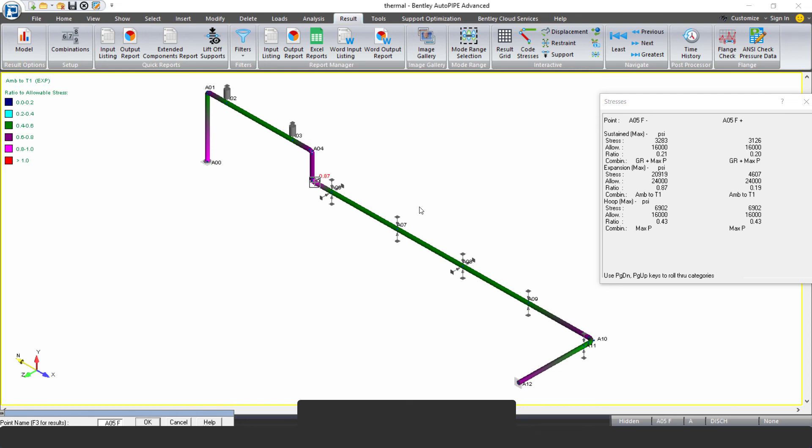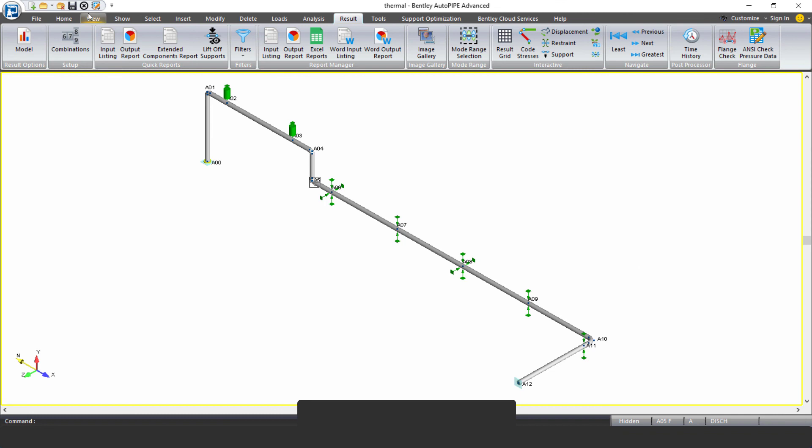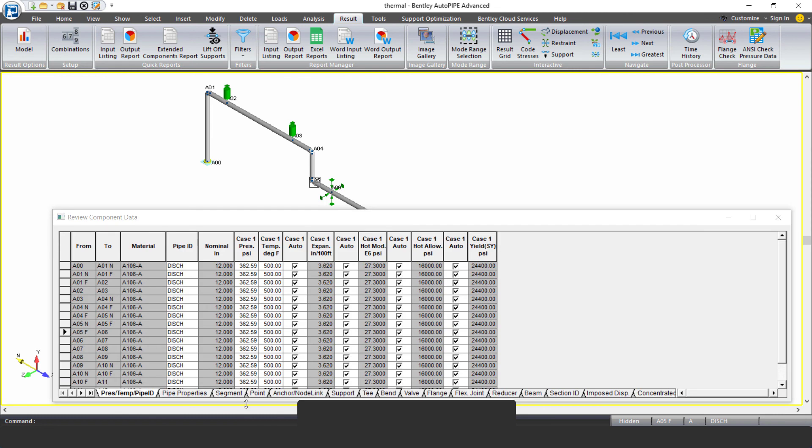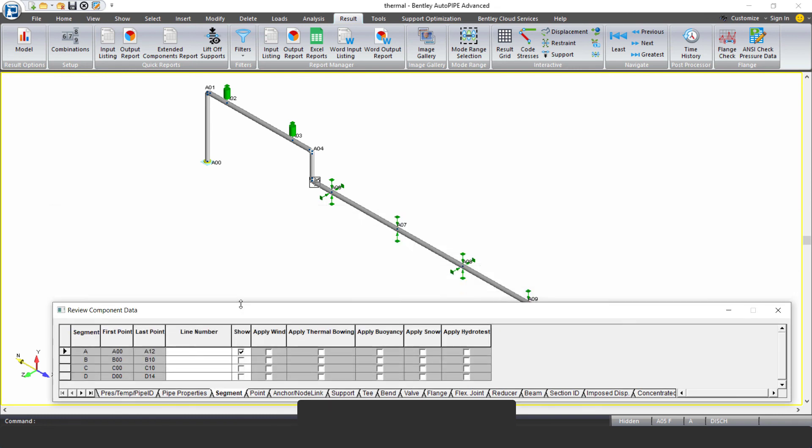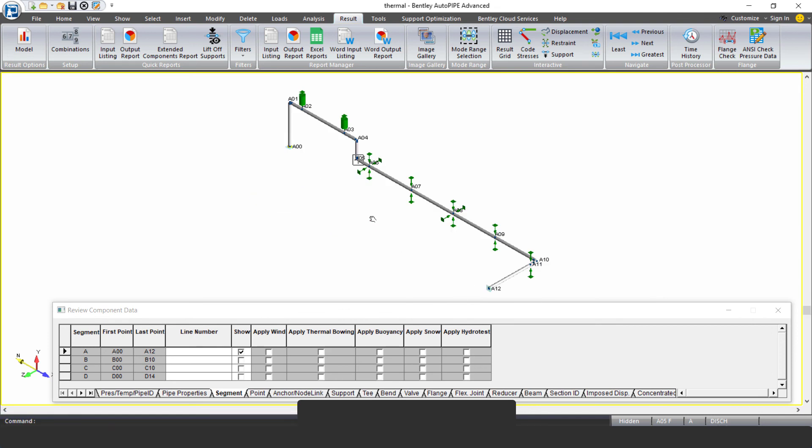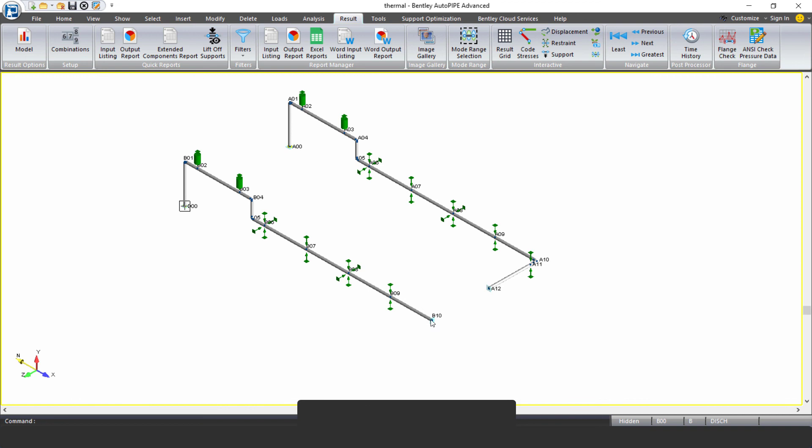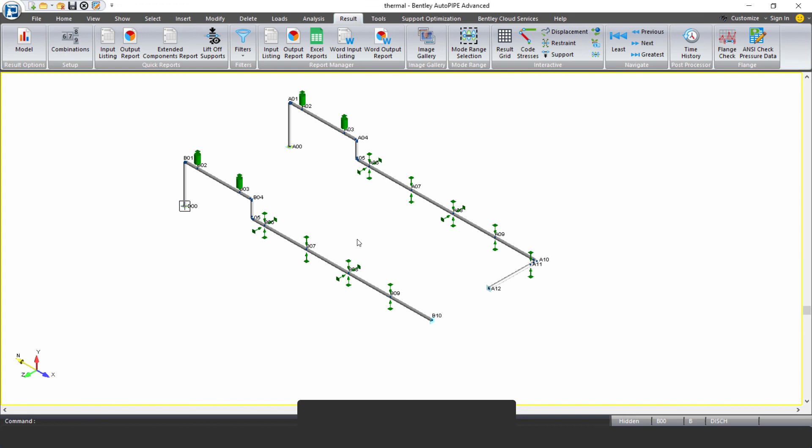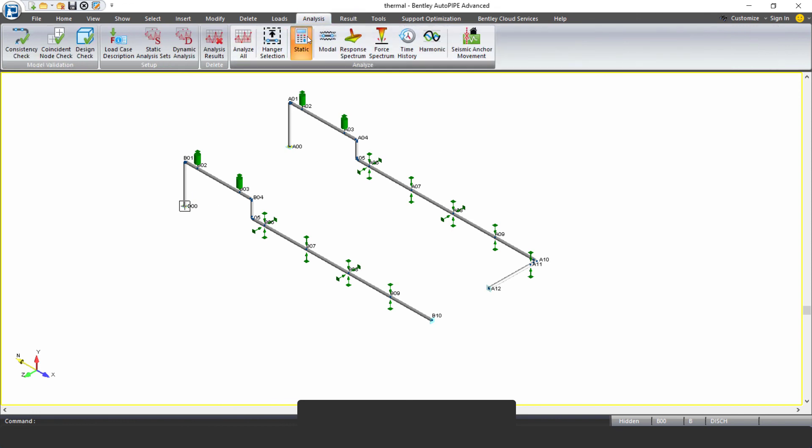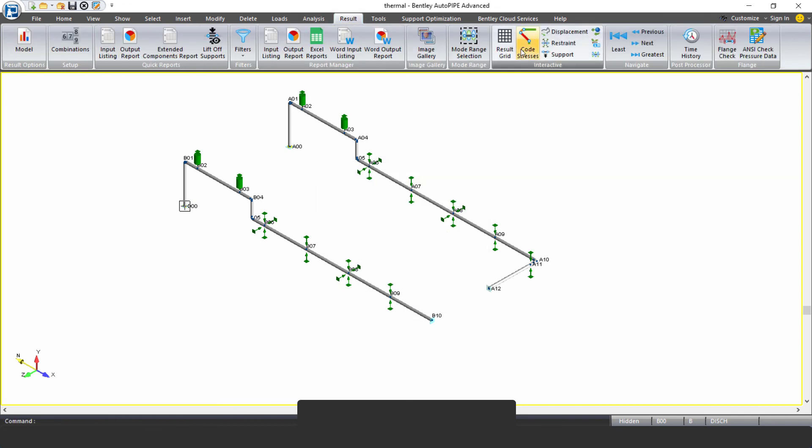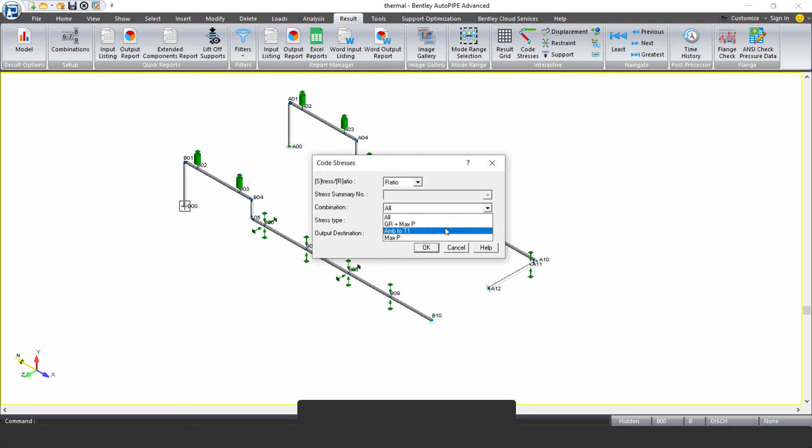We're going to work with this model and take it another step further. So if I come and turn on, I have a couple of segments modeled in here. So let's turn them on one by one. This is segment A. If I turn on segment B, all I've done in segment B is I've taken away just this small section of piping. Well, this small section of piping is doing a lot for us flexibly. It's allowing the pipe much more flexibility than when you take out that small section of piping. And now everything horizontal is in the x direction. So we don't have any bend over here to take some thermal growth, which we had previously. And so we may run into some issues. We probably will run into some issues. Everything's growing this way and this way, and that's going to cause some problems. We have some upward growth. The springs are allowing that. But other than that, everything's along the one axis.